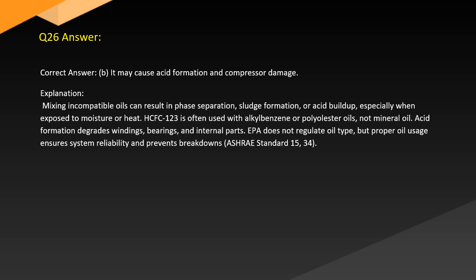Answer. Correct answer: B. It may cause acid formation and compressor damage. Explanation. Mixing incompatible oils can result in phase separation, sludge formation, or acid buildup, especially when exposed to moisture or heat. HCFC-123 is often used with alkyl benzene or polyolester oils, not mineral oil. Acid formation degrades windings, bearings, and internal parts. EPA does not regulate oil type. Proper oil usage ensures system reliability and prevents breakdowns. ASHRAE Standard 15, 34.